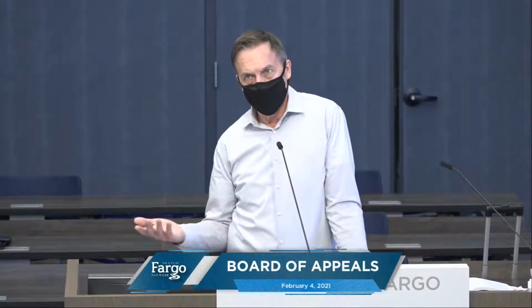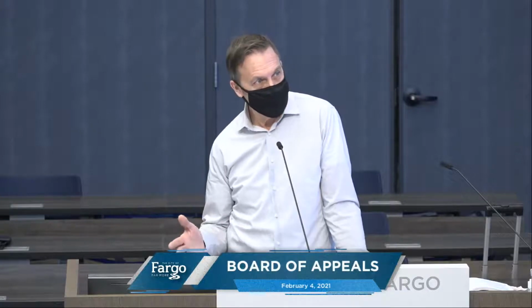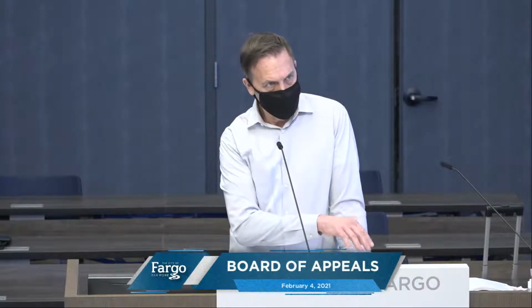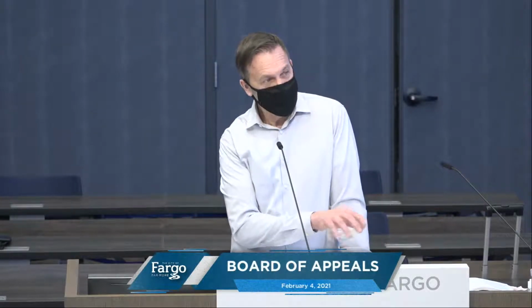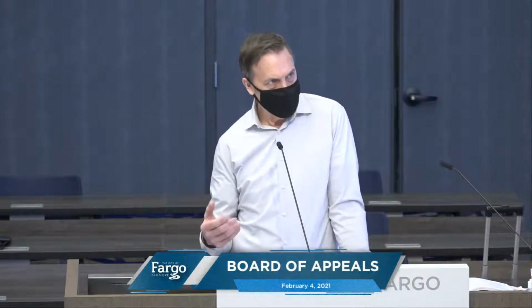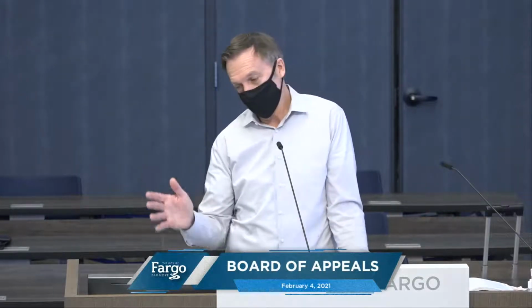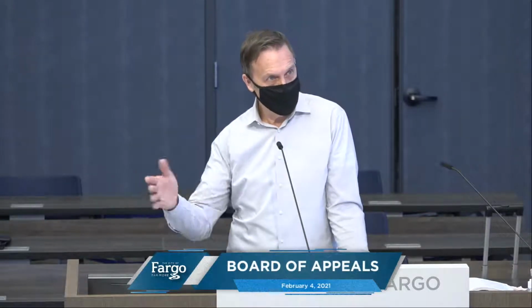Normally we have some general rules, like you don't just stop a sprinkler system. There are some specific areas in the code that have areas where you can sprinkle or not. This one isn't in there. We could look at it like that, but normally we would say, if you sprinkle a little space, you're going to provide a fire barrier anyway to separate a sprinklered area from a non-sprinklered area in a building. We always say that you need something to stop a sprinkler.